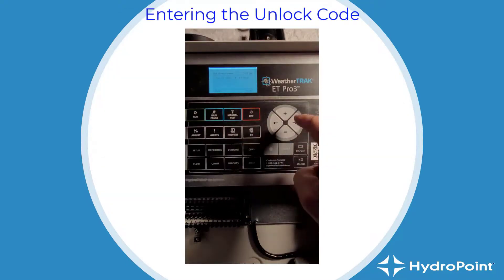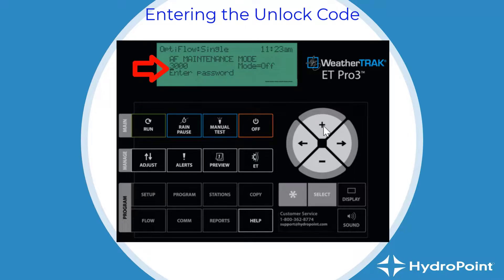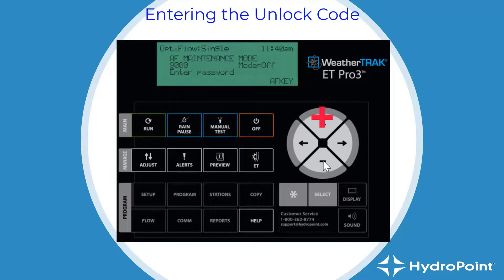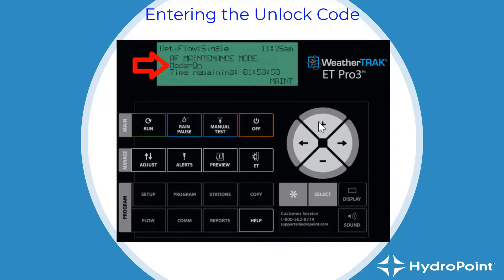Once you've found that code, take it to the controller and manually enter the unlock code into the panel to gain access to the maintenance features. At the panel, start by hitting the Run button to go to the Run screen. Then press the forward arrow and it will take you to a screen that says 'AF Maintenance Mode' — this is where you enter the four-digit code. Be mindful of the cursor. Use the plus and minus buttons to select the right digit in the first column, then use the forward arrow to move the cursor to the second column and repeat. Go through all columns selecting the proper code, and when you enter the correct unlock code, the panel will immediately unlock.